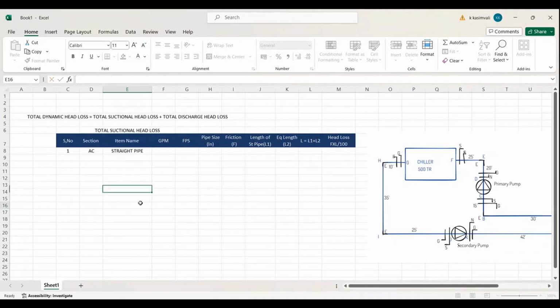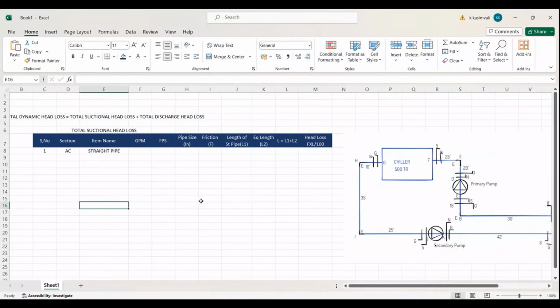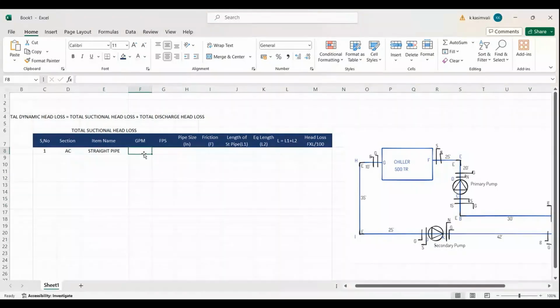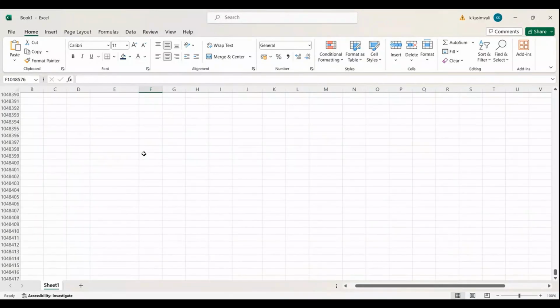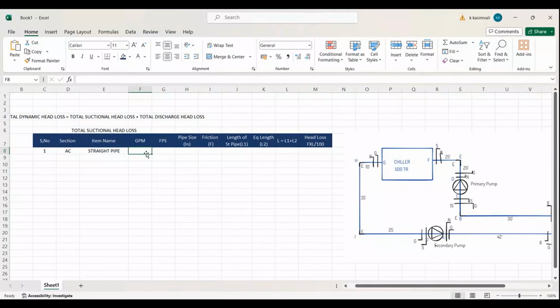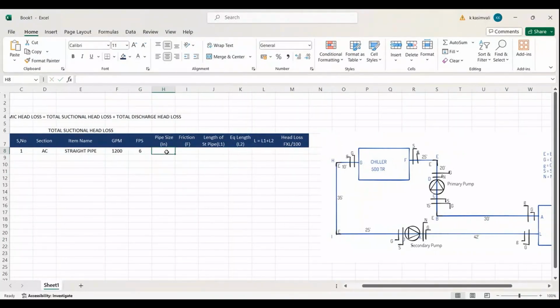Total suction head loss. As it is a straight pipe, what is the GPM value? We are taking GPM as 1200, right? FPS, how much have we taken? We have taken it as 6. What pipe size did you get? 10 inches. 1.25. Length of straight pipe is 30 plus 15, 45. Equivalent length 0. So that equivalent length, I'll tell you what it is.